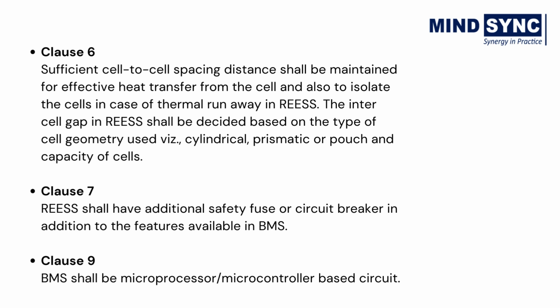Sufficient cell-to-cell spacing distance shall be maintained for effective heat transfer from the cell and also to isolate the cells in case of thermal runaway in battery. The inter-cell gap in battery shall be decided based on the type of cell geometry used. Battery shall have additional safety fuse or circuit breaker in addition to the features available in BMS.